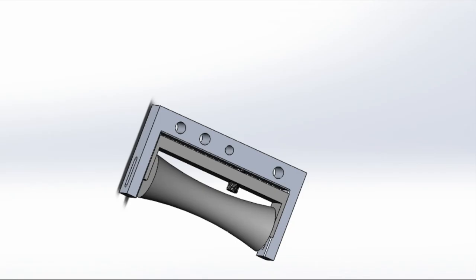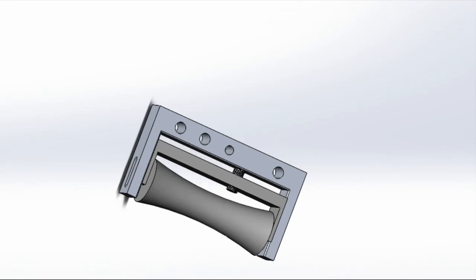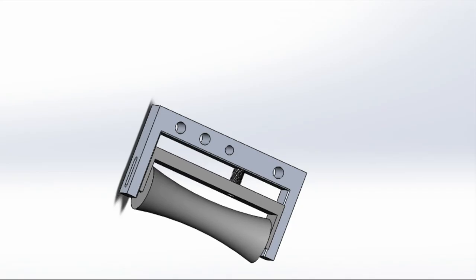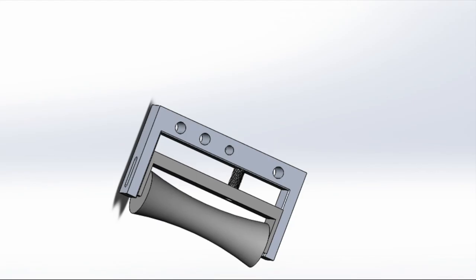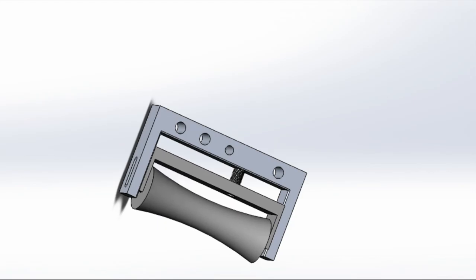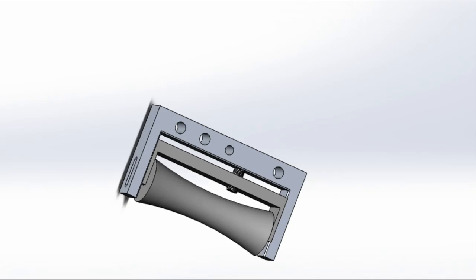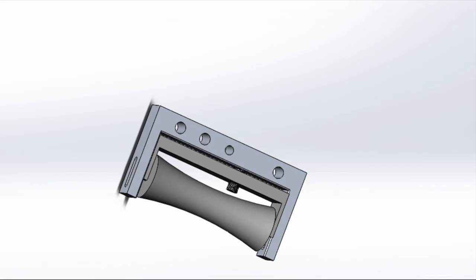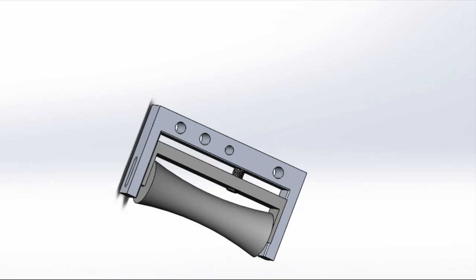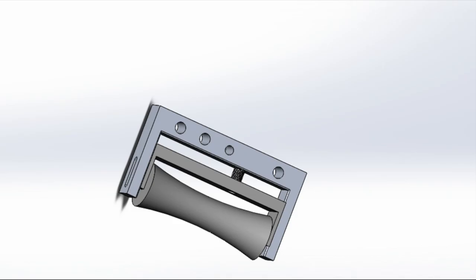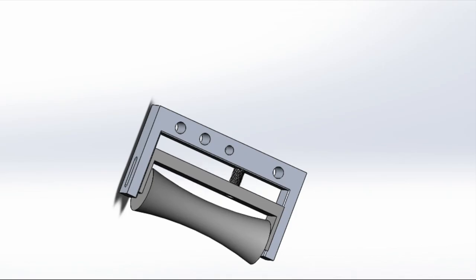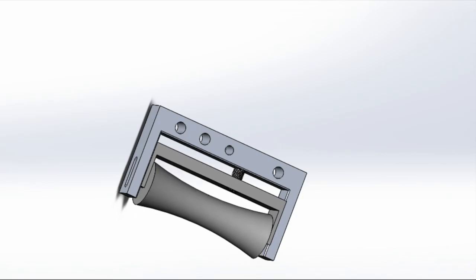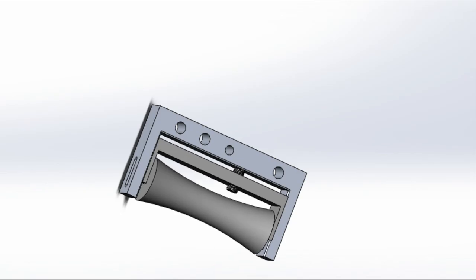Lastly, the massaging unit will consist of a 3 inch roller connected on both ends to a steel bracket. This bracket will be mounted inside the larger guide bracket with rails to allow the smaller bracket along with the roller to move up and down. Through the top of both brackets will be the lead screw of another stepper motor. This motor will be mounted to the top of the guide bracket and will move with the unit forward and back. Between both brackets attached to the lead screw will be another load cell to measure pressure on the forearm. This motor and load cell configuration is the same as the hand, except the maximum recommended pressure for the arm is 40 pounds.